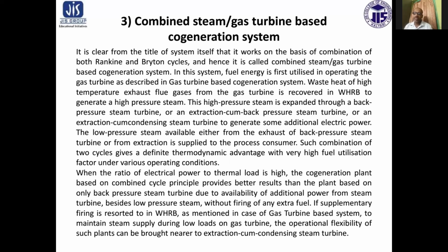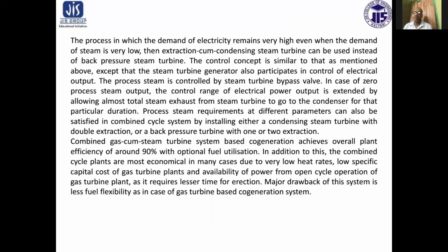Without firing of any extra fuel, if supplementary firing is resorted to in the waste heat recovery boiler, as mentioned in the case of gas turbine based system, to maintain steam supply during low load of the gas turbine, the operational flexibility of such plants can be brought nearer to an extraction cum condensing steam turbine. In a process in which the demand of electricity remains very high even when the demand of steam is very low, an extraction cum condensing steam turbine can be used instead of a back pressure steam turbine.